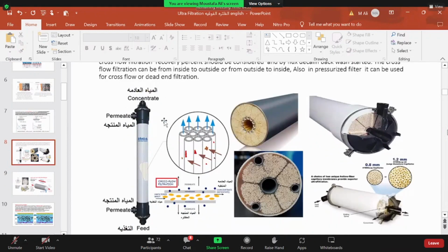It can be used for filtration, for industrial water treatment, to remove some chemicals or high molecular weight compounds, where the diameter of the hollow fiber itself is not an issue. Or it can be used to treat turbid water, surface water like river water, water with contaminants, or even wastewater treatment like in the MBR, as we will see in the applications.